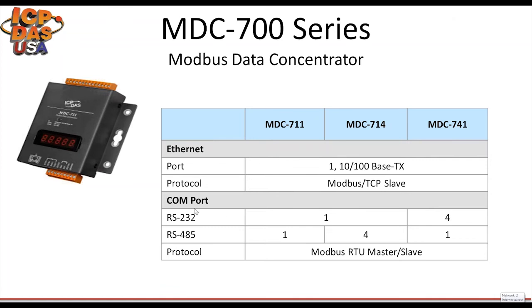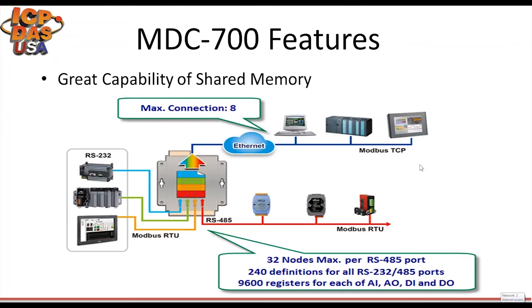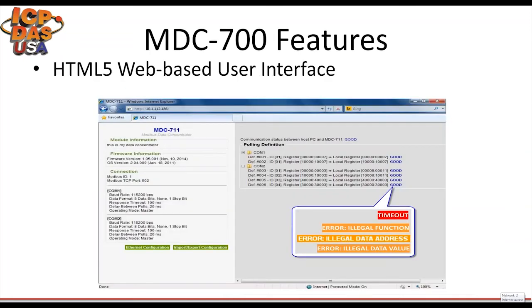We have MDC 711, 714, and 741, which have different numbers of RS-232 and RS-485 ports. The MDC 700 module can perform up to 240 Modbus RTU commands from Modbus slave devices through RS-232 or RS-485. Up to eight Modbus TCP masters are allowed to get the pooled data through the Ethernet. The internal shared memory has four tables to store AI, AO, DI, and DO data, and each table can store up to 9600 registers.